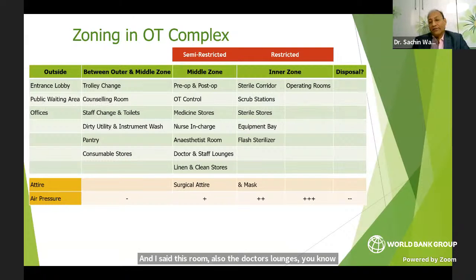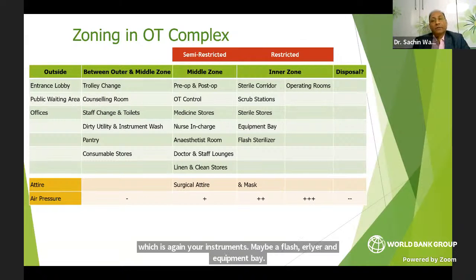The final area is the inner zone, where you have the sterile corridor. The sterile corridor does not have anything else except the scrub stations and the operating room. Anything additional you could have is the sterile stores, for instruments, maybe a flash sterilizer, and an equipment bay.